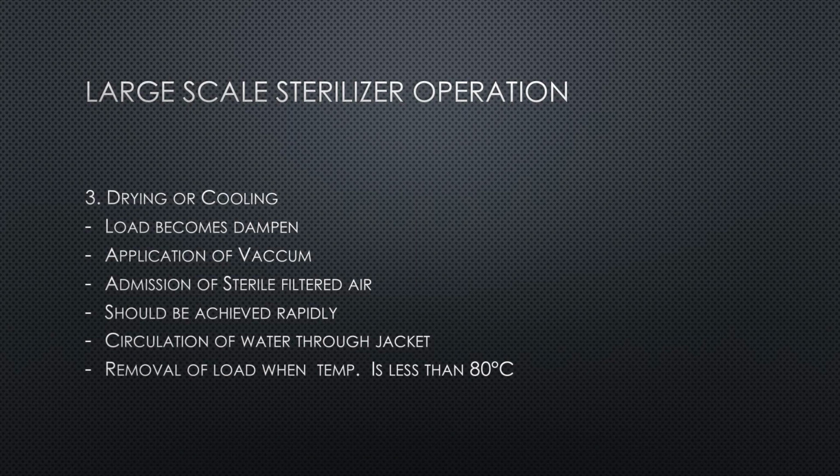Containers must not be removed from the sterilizer until the internal temperature is brought to a safe level, that is less than 80 degrees Celsius. So we should not be in a hurry to remove the articles just because the sterilization cycle is over. We have to wait till the chamber achieves a temperature less than 80 degrees Celsius, and then we should open the doors, because otherwise it may cause an explosion. So we have to avoid that.